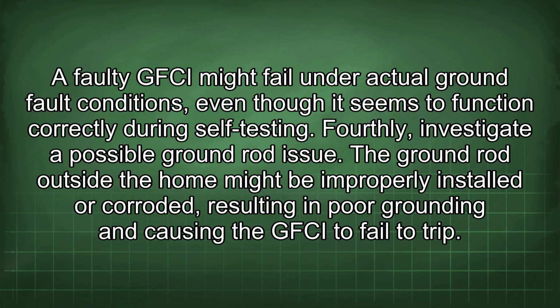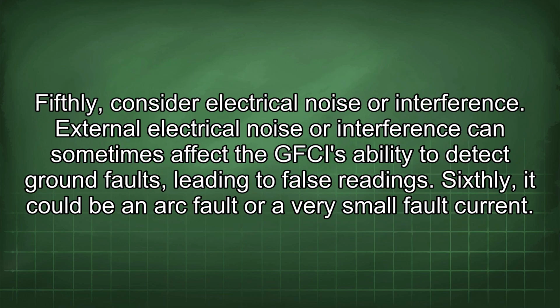Fourthly, investigate a possible ground rod issue. The ground rod outside the home might be improperly installed or corroded, resulting in poor grounding and causing the GFCI to fail to trip. Fifthly, consider electrical noise or interference. External electrical noise or interference can sometimes affect the GFCI's ability to detect ground faults, leading to false readings.